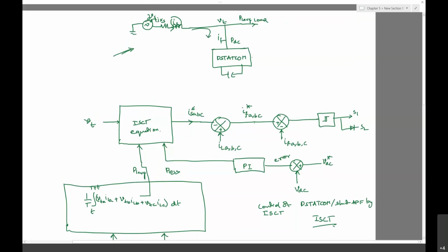How is the D STATCOM power rating to be fixed? These are the ratings to be fixed. We need to design for the worst case of the load which is to be connected. The rating of the DC link voltage is 2 times the supply peak voltage. The filter L is to eliminate the switching frequency component and has to be designed too. The design part is not much difficulty and is very well available in the literature.